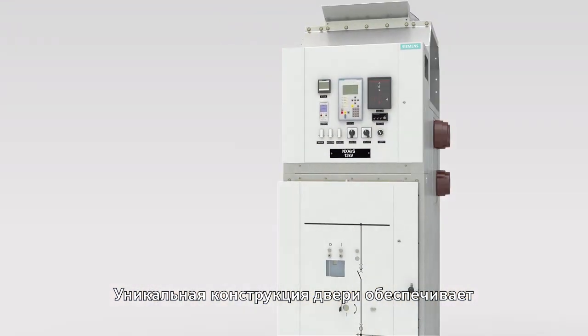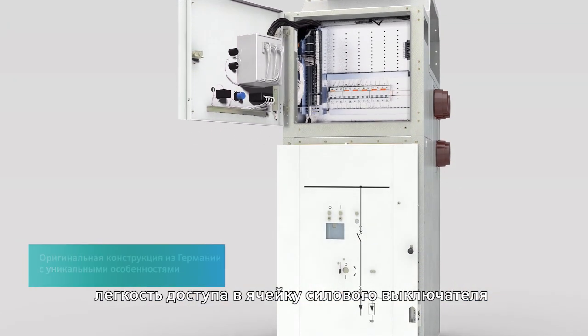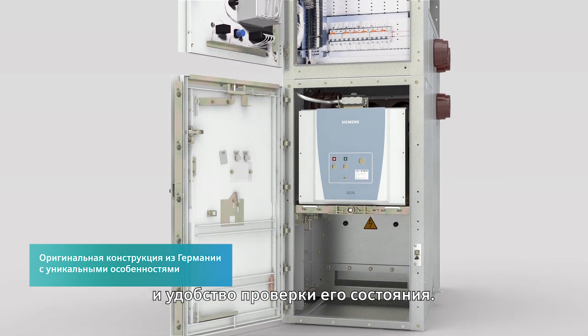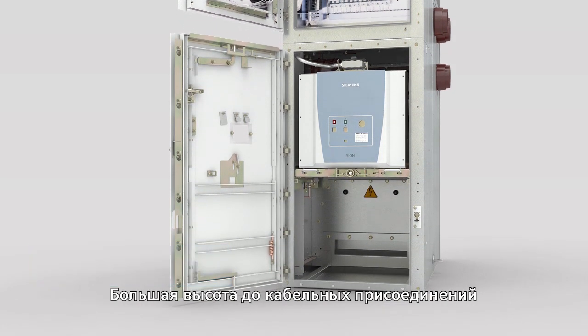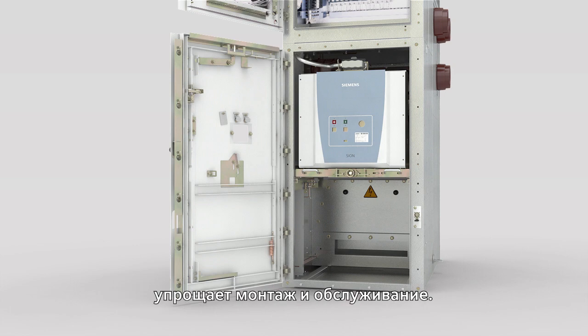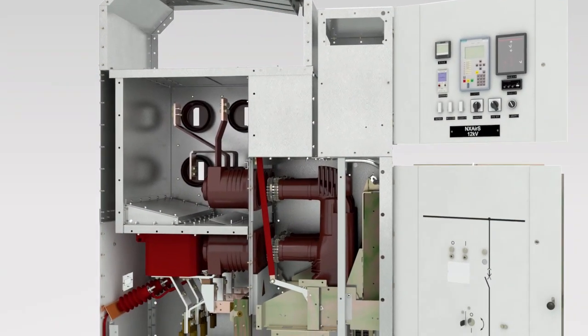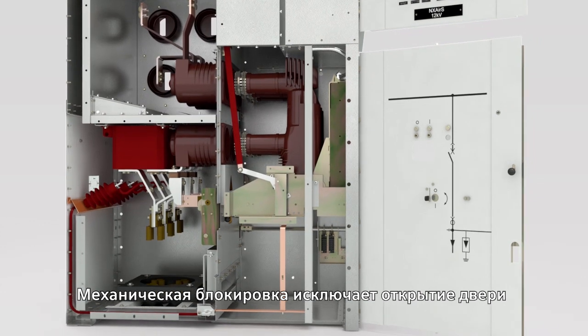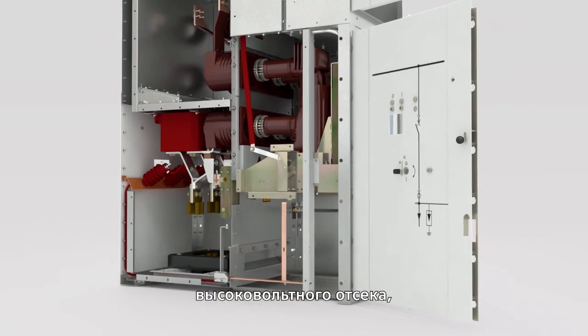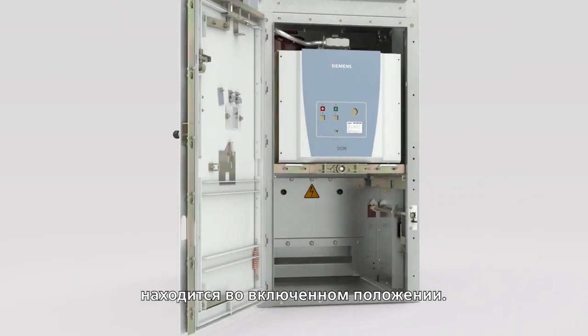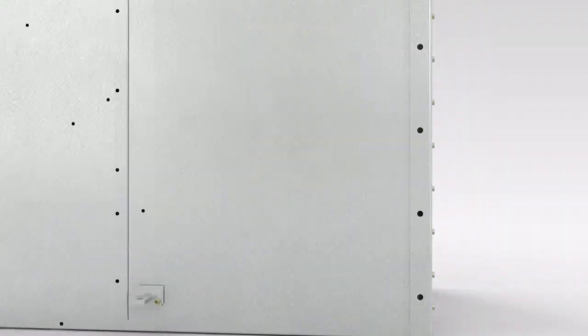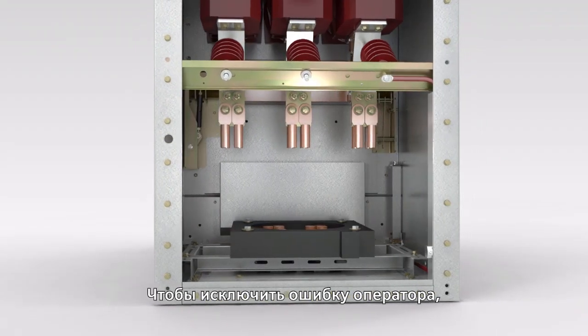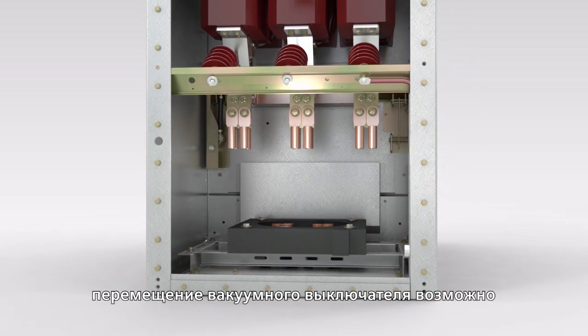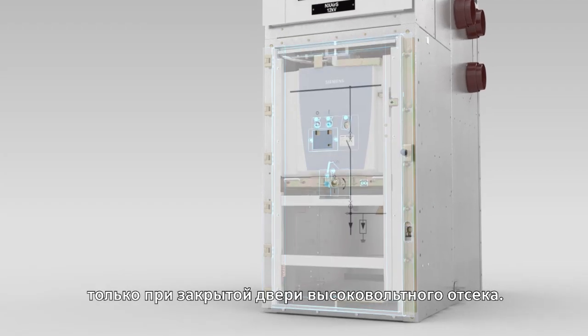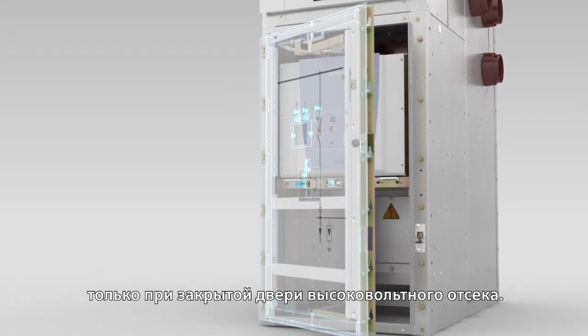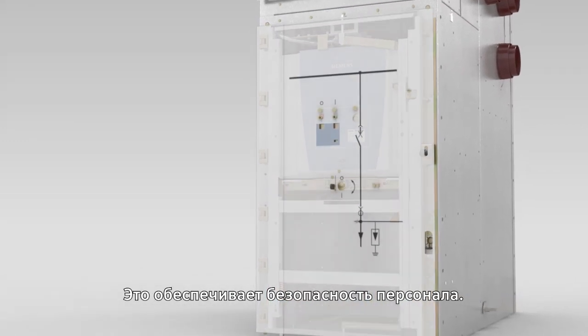Unique door design enables easy access to the circuit breaker compartment and convenient execution of condition checks. High cable terminals will ease the installation and maintenance. The mechanical interlocking blocks the opening of the high voltage door while the vacuum circuit breaker is not in disconnected position. The vacuum circuit breaker can only be racked in while the high voltage door is closed to prevent maloperation by the operator. This ensures personnel safety.